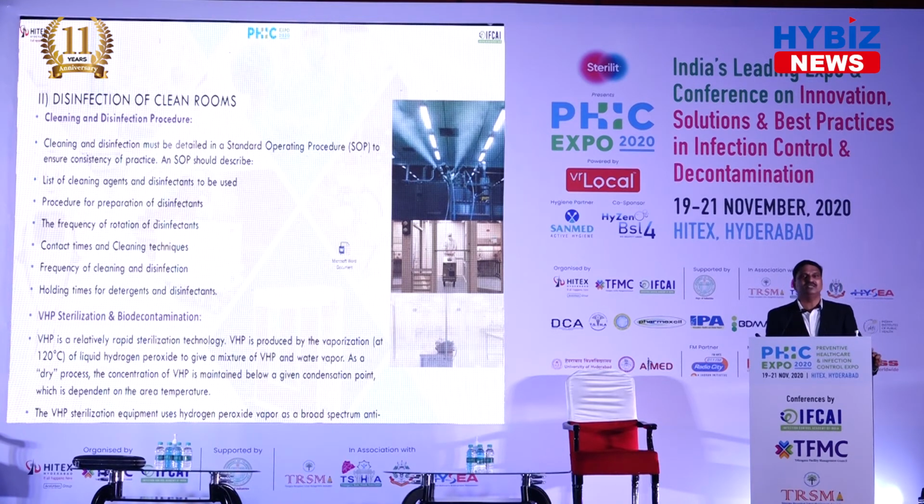During this VHP sterilization process, the vapors will be spread throughout the clean rooms, and biological indicators of more than 10 to the power of 6 cells will be challenged, and the efficacy will be evaluated. This is a recent technology; since the last decade, or otherwise since 3-4 years, the pharma industry started using this. It is a very effective mode of disinfecting clean rooms, and I think this is the future of clean room disinfection.